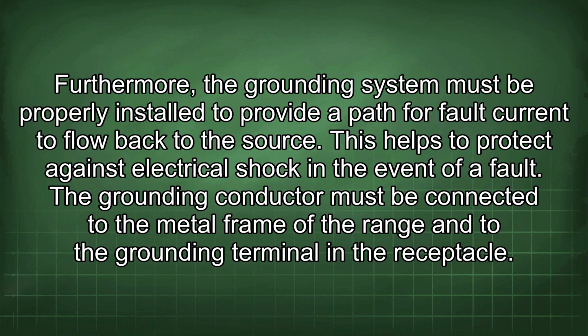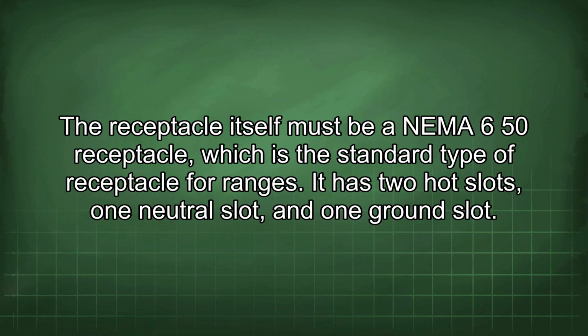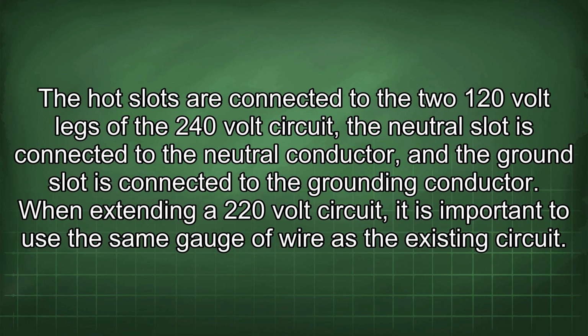Furthermore, the grounding system must be properly installed to provide a path for fault current to flow back to the source. This helps to protect against electrical shock in the event of a fault. The grounding conductor must be connected to the metal frame of the range and to the grounding terminal in the receptacle. The receptacle itself must be a NEMA 6-50 receptacle, which is the standard type of receptacle for ranges. It has 2 hot slots, 1 neutral slot, and 1 ground slot. The hot slots are connected to the two 120-volt legs of the 240-volt circuit. The neutral slot is connected to the neutral conductor, and the ground slot is connected to the grounding conductor.